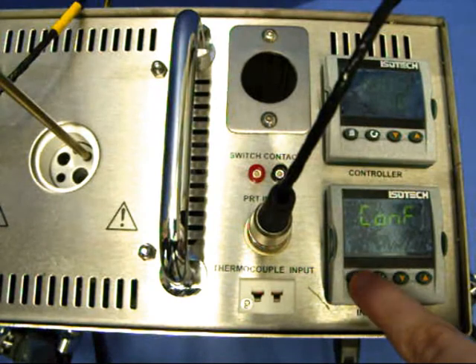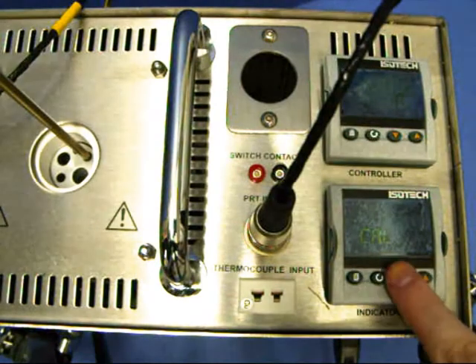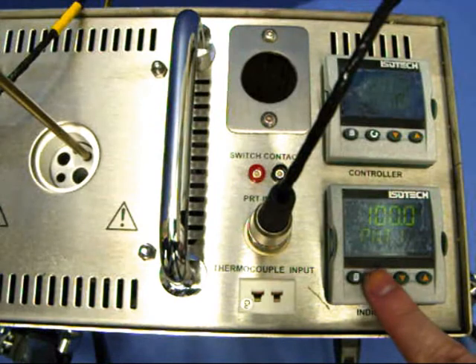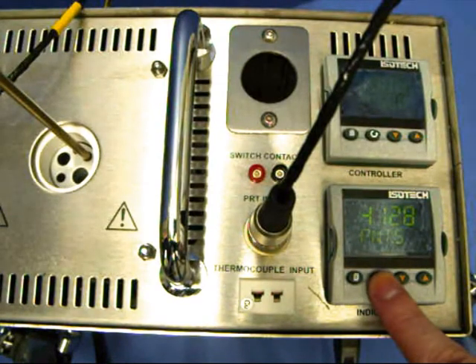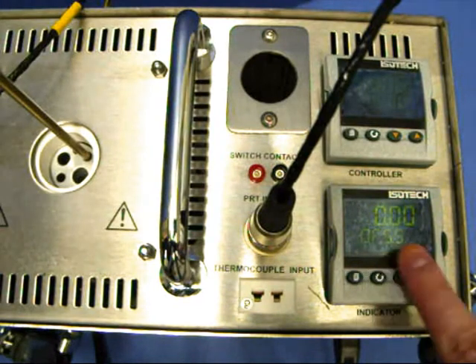Press the page key until the controller shows CAL. Now use the scroll key to examine the data pairs. The values 0.1 through to 0.5 and offset 1 through to offset 5 can be modified with the up and down keys.